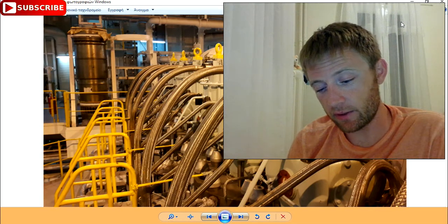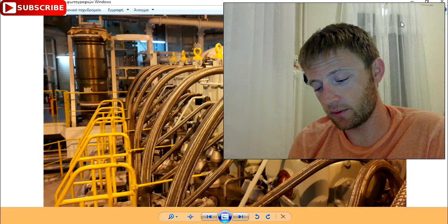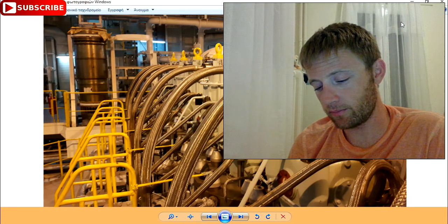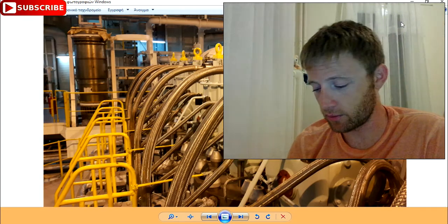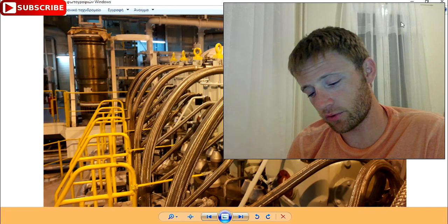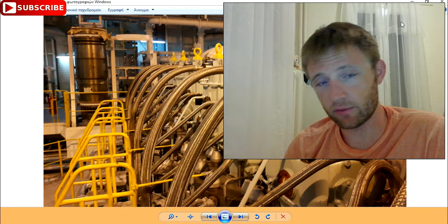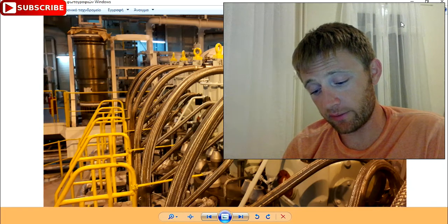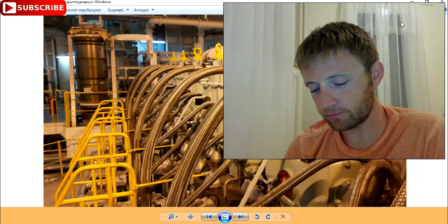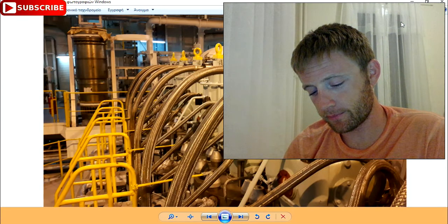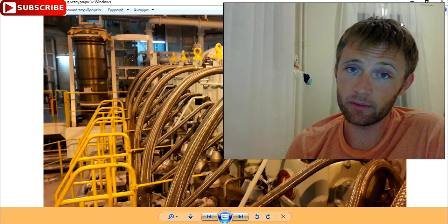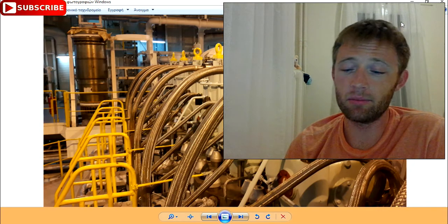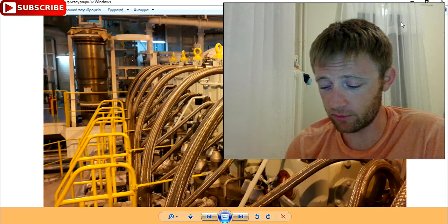And number 10 here is when the alarm hits and you hear this oil filter alarm, that means it's clogged, okay? You can continue your discharge, and after you finish discharging, you can change it, okay? Number 11. All the other alarms, you must fix them, okay? If you have this kind of differential pressure alarm of oil, you can discharge, okay? But if any other alarm comes, you need to fix it.